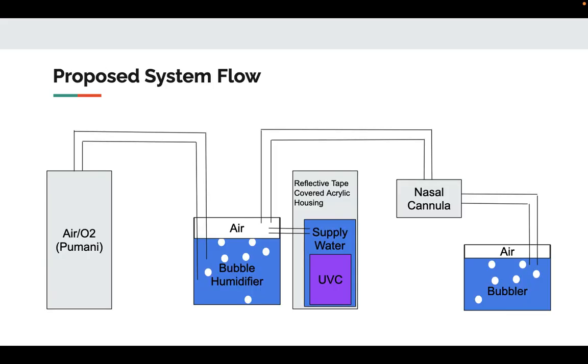So our proposed system flow is the air and O2 coming from the Pumani, going through the bubble humidifier, which is supplied with a water supply that has been UVC sterilized. This UVC subsystem includes reflective tape and covered acrylic housing to prevent exposure of any individuals to harmful UVC radiation. This humidified air will go from the bubble humidifier to the nasal cannula, and the nasal cannula will be connected to the bubbler, which is at the end of the bubble CPAP, and this creates a closed system and helps regulate pressure throughout the system.